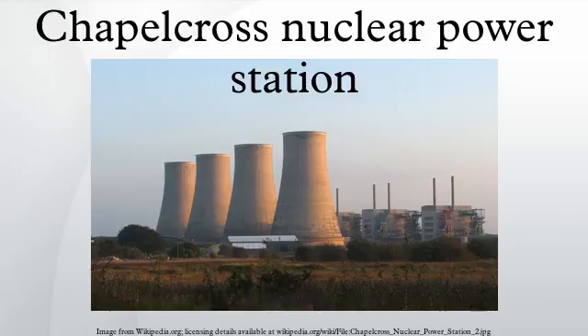Single channel fuel clad melt: fuel in a single channel in Reactor 2 that was loaded with fuel elements under evaluation for the commercial reactor program experienced a partial blockage, attributed to the presence of graphite debris. The fuel overheated and the Magnox cladding failed, causing contamination to be deposited in one region of the core.